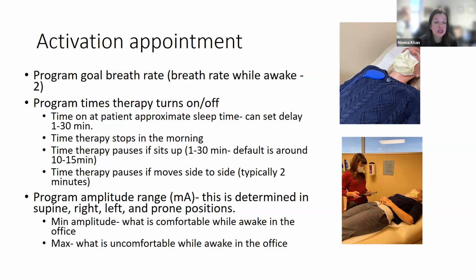And then in terms of when you turn the therapy on and off, you want to make it a time that the patient thinks that they fall asleep, and you can set a delay. So let's say they go to bed at 11. You can also set a 30-minute delay that gives them time to fall asleep. That way they're getting into bed at 11, but if they don't fall asleep until 11:30, therapy doesn't kick on until that time. You program a time where therapy stops in the morning, and then you program the amount of pause time if they sit up or move around. When they sit up, it can be anywhere from 1 to 30 minutes, but generally we make this 10 to 15 minutes. And the pause, if they turn side to side, we usually make around 2 minutes.